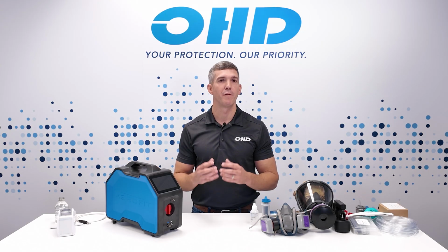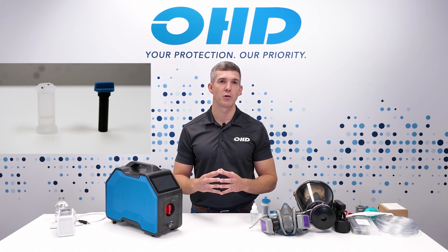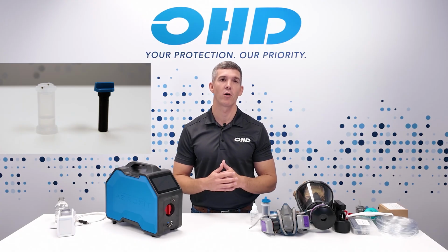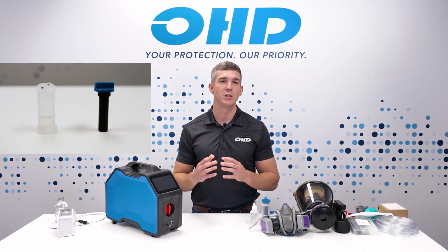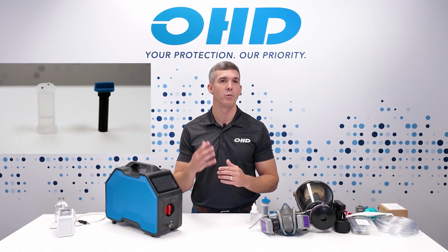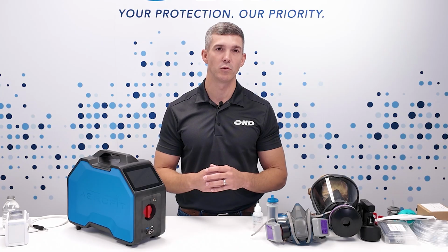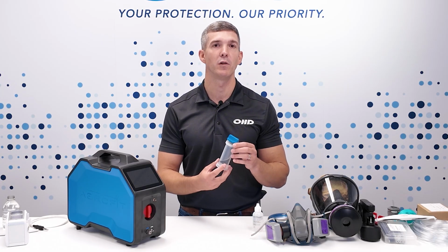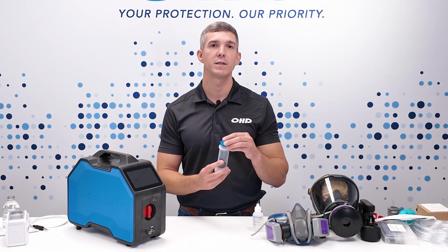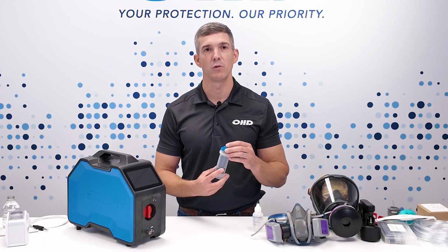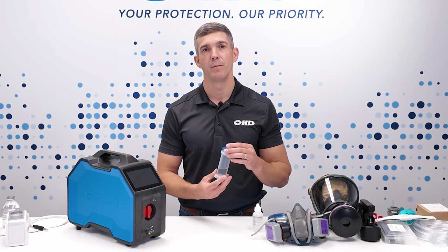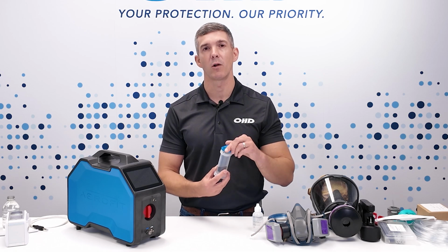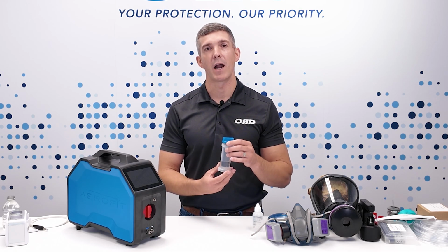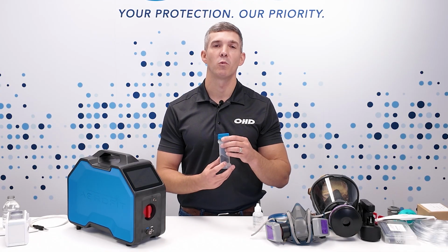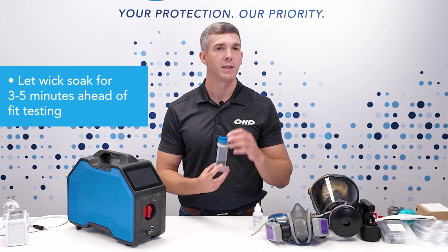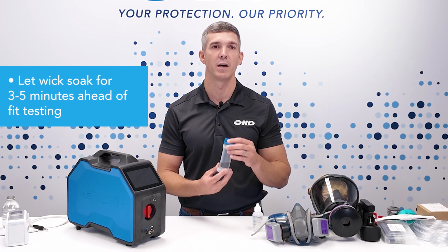Before turning on the AeroFit, there are a few steps we recommend completing. First, ensure the wick within the wick assembly is charged with alcohol inside the storage capsule. To do this, fill the capsule with reagent-grade alcohol, which is provided. Remove the wick assembly from the capsule and fill the reservoir at a minimum to the fill line marked alcohol window, and then reinsert the wick assembly. Don't overfill the capsule more than halfway, as the alcohol will overflow. Once the wick assembly is reinserted, turn it clockwise to lock it into place, making sure the bottom of the wick is fully submerged. This allows the wick to absorb alcohol before fit testing. It's important to remember to let the wick soak for 3 to 5 minutes ahead of fit testing.